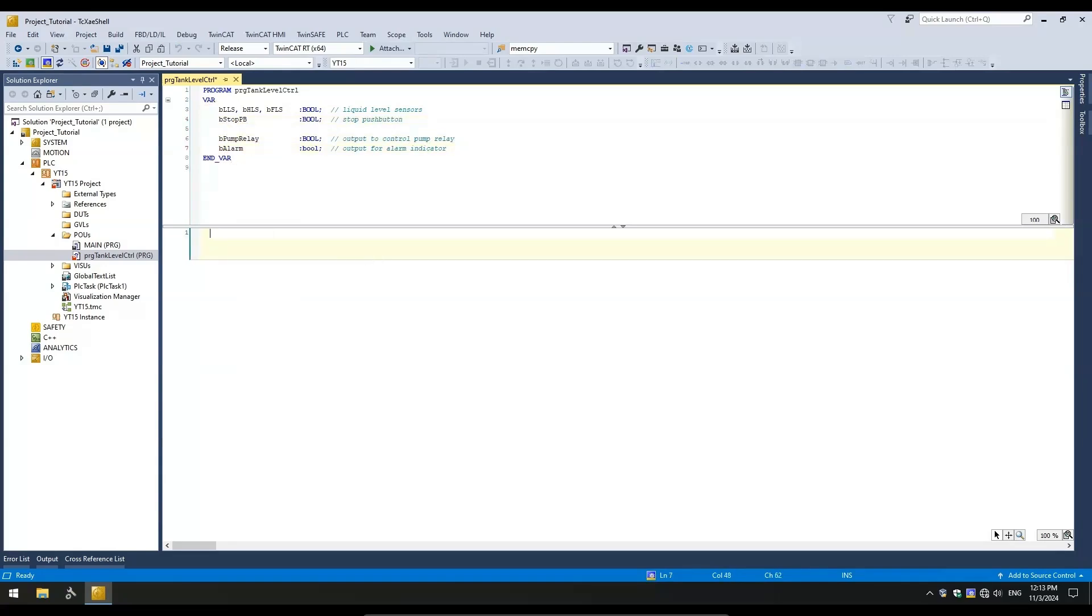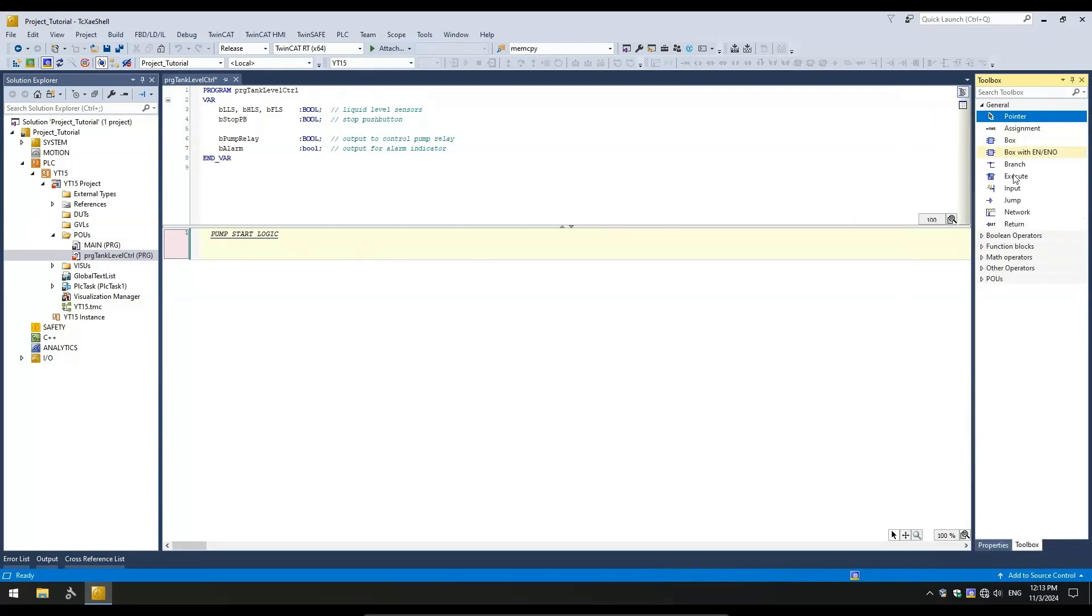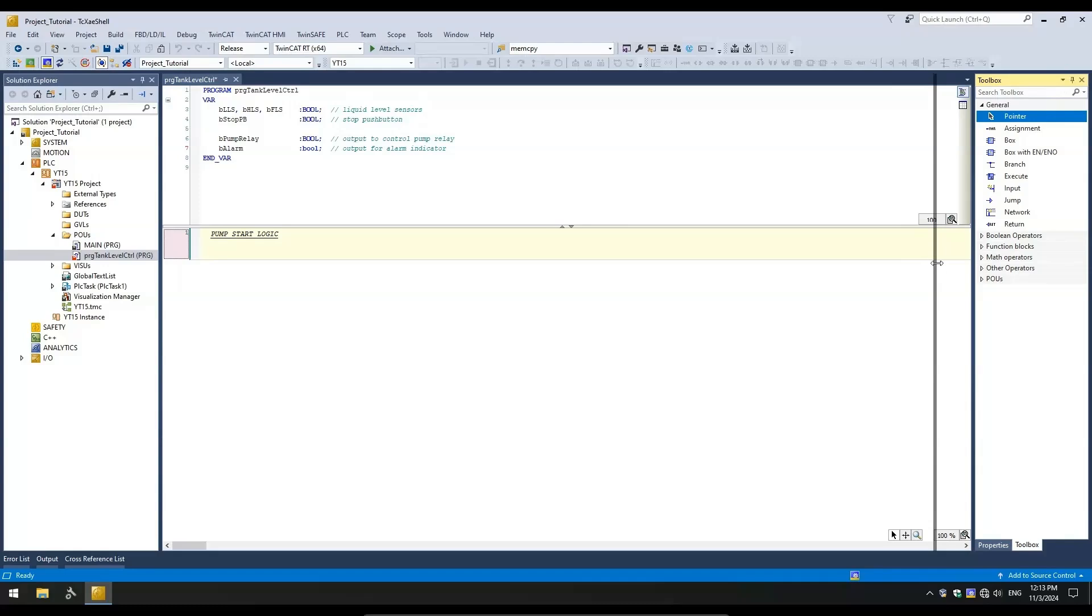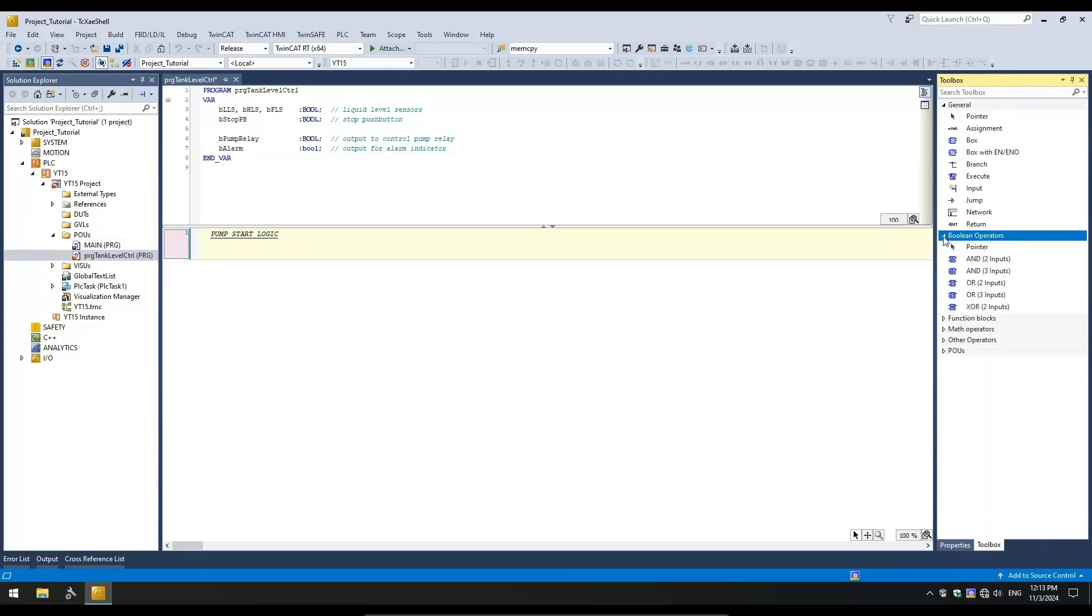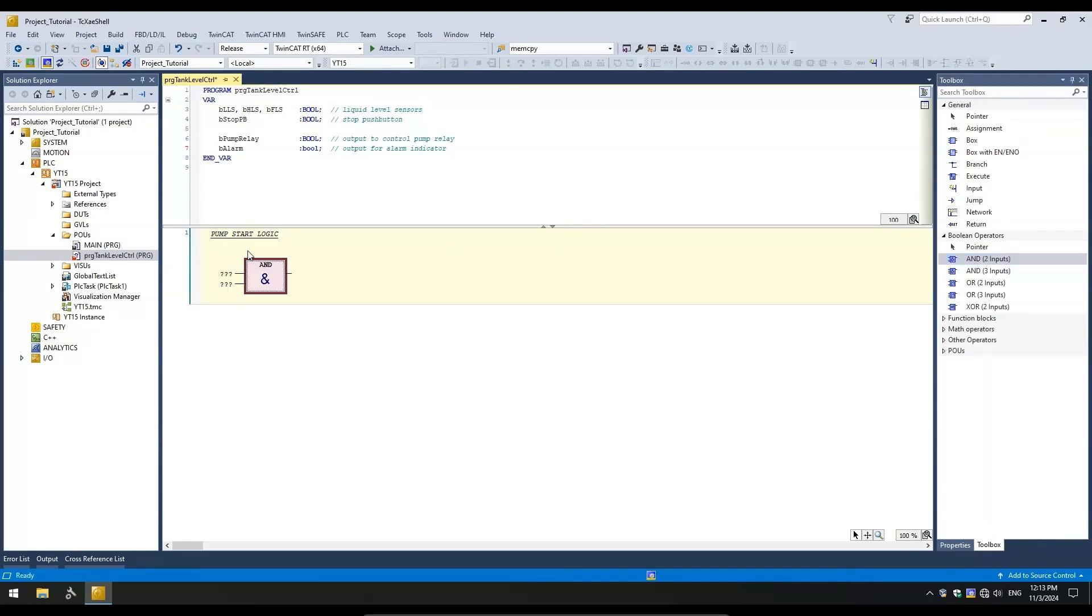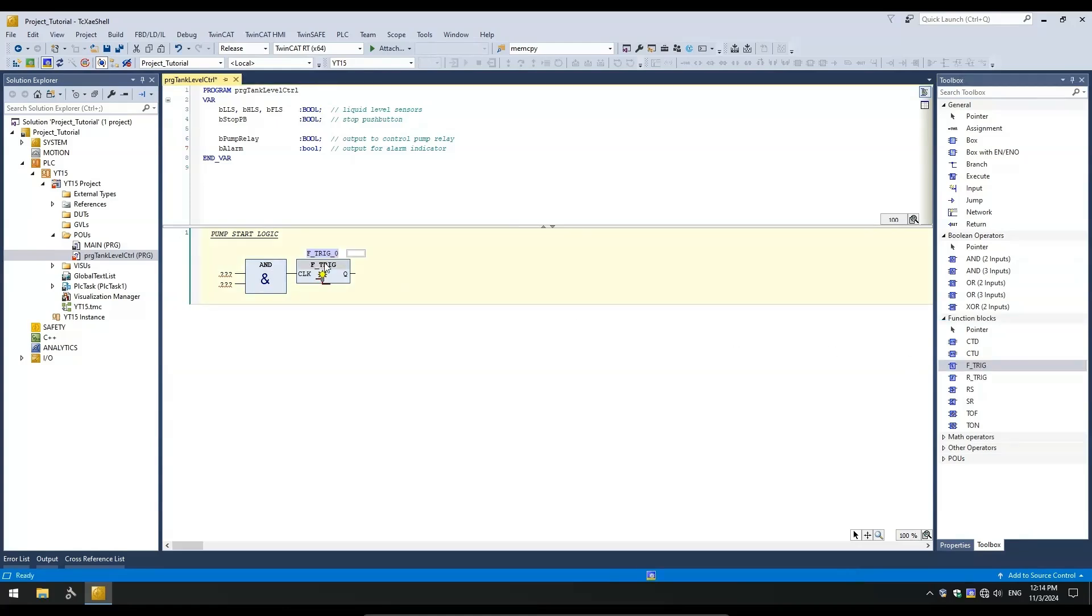Now, I will implement the PumpStart logic. When the tank liquid level is low, the high level sensor will be off, and only the low level sensor will be on. As the tank empties, the low level sensor will eventually turn off. We can use these conditions to start the pump. In other words, the PumpStart condition is no HLS signal and a falling edge on LLS signal. We will use these conditions to set the pump output bit. For this, we will need an AND operator and a falling edge trigger for the low level sensor.